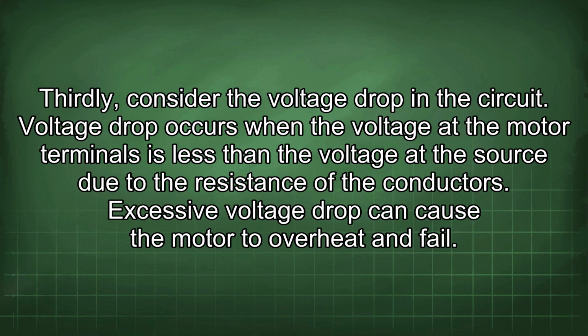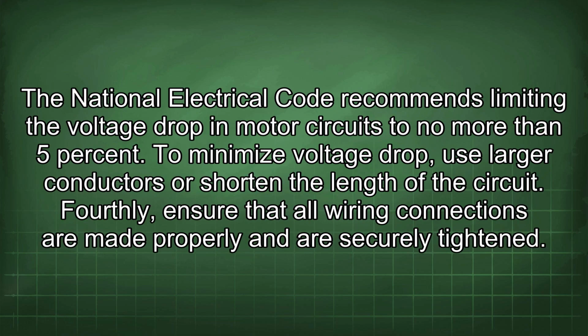Thirdly, consider the voltage drop in the circuit. Voltage drop occurs when the voltage at the motor terminals is less than the voltage at the source due to the resistance of the conductors. Excessive voltage drop can cause the motor to overheat and fail. The National Electrical Code recommends limiting the voltage drop in motor circuits to no more than 5%. To minimize voltage drop, use larger conductors or shorten the length of the circuit.